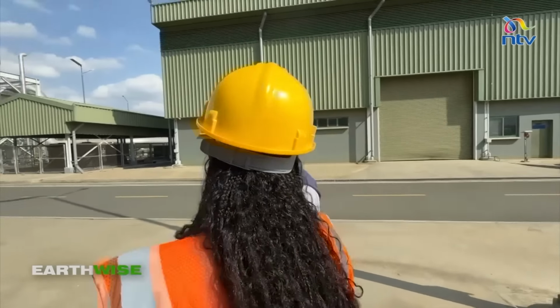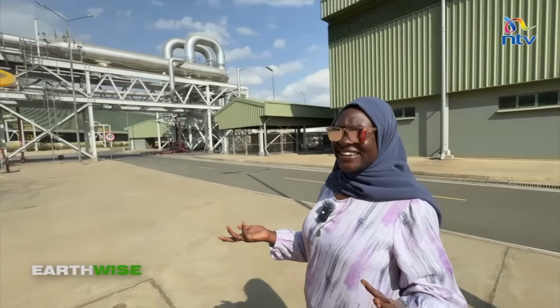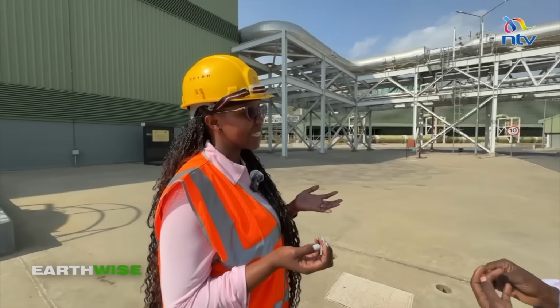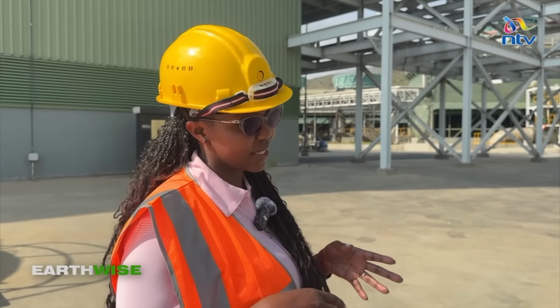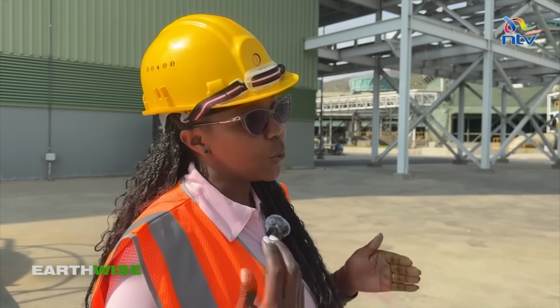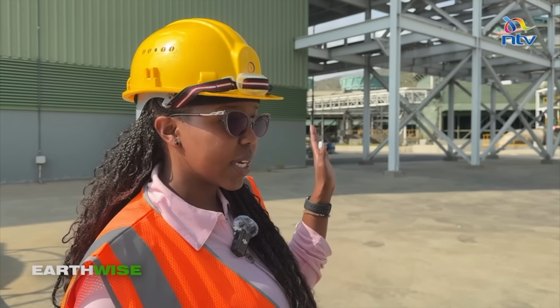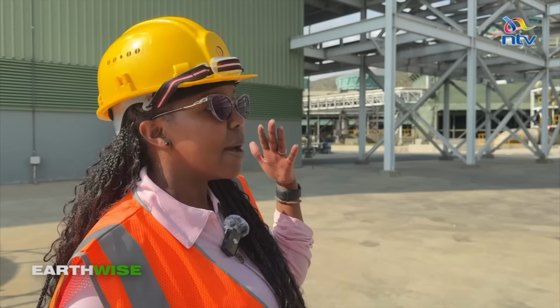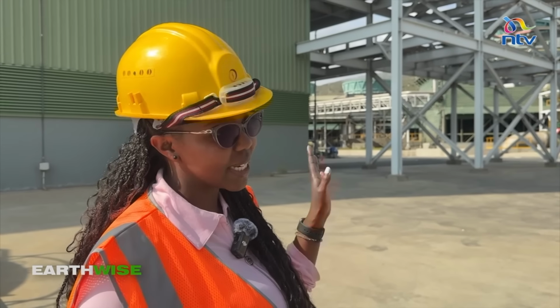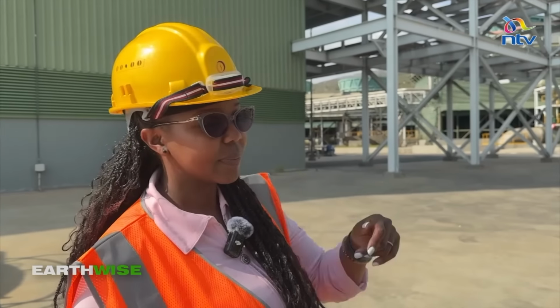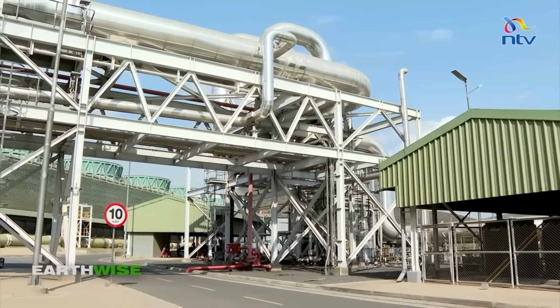What do you mean dry? How do you dry steam? Isn't it already wet? What we mean by dry is in terms of saturation. We can have saturated steam and steam that is non-saturated. As the steam travels from the wells, it generally condenses, changing form from steam to liquid. So before it goes into the steam turbine, we need to make sure it's as dry as possible. Dry means no water, no condensate in it.